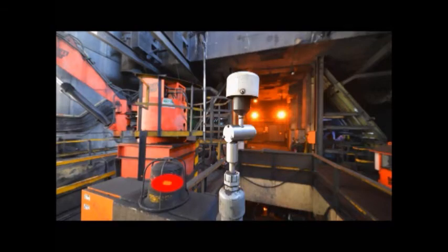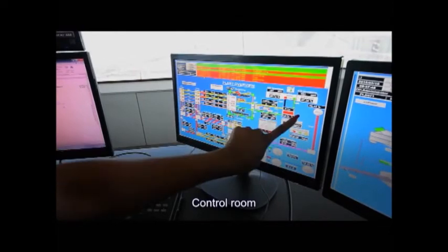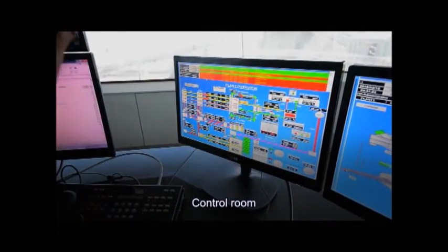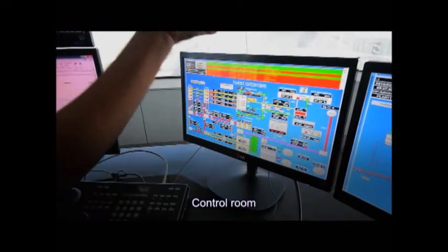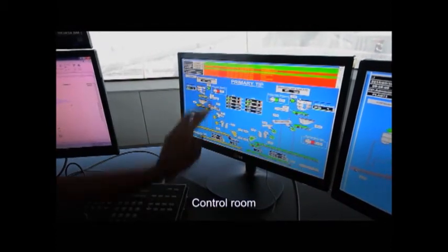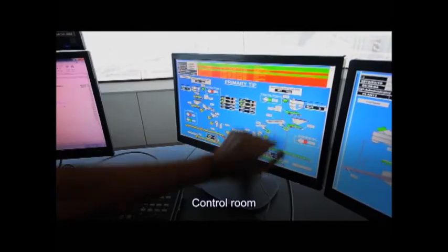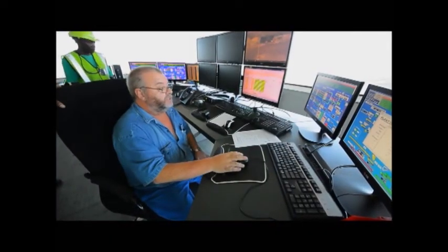This is our dust suppression; that is our e-sampler from the primary tip — that is where we see if maybe a dust level is going up or even going down. Whenever we have it going up, our feeder will stop — either A11 or A12, which is A11 for stream 1 and A12 for stream 2. Certain alarms are generated by the real-time dust monitor e-sampler, and these alarms are raised in the central control room.